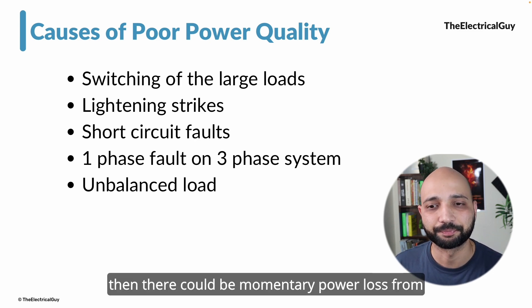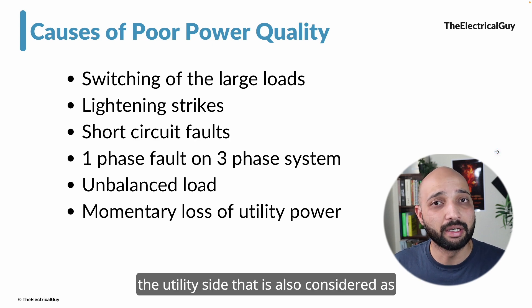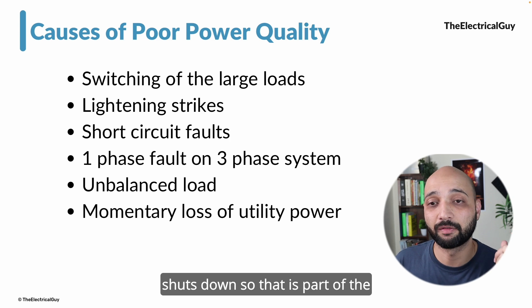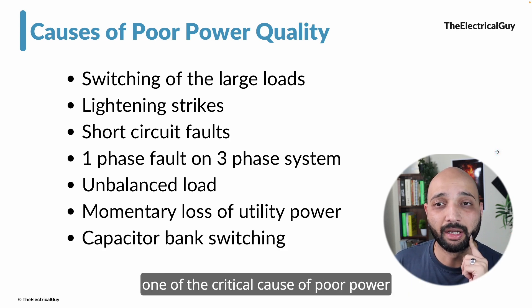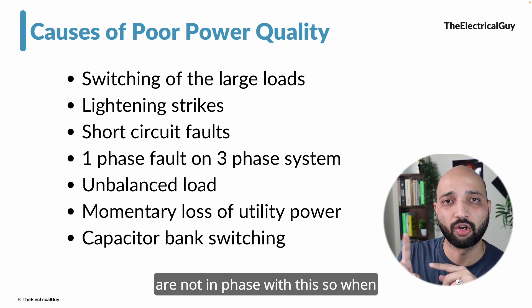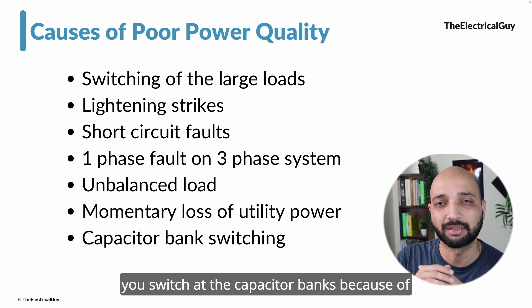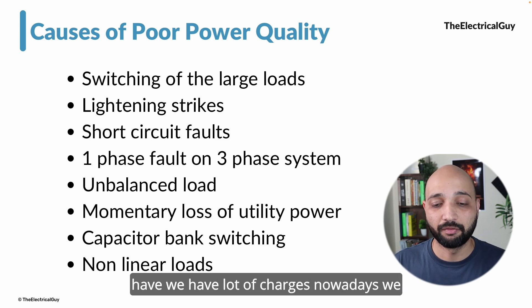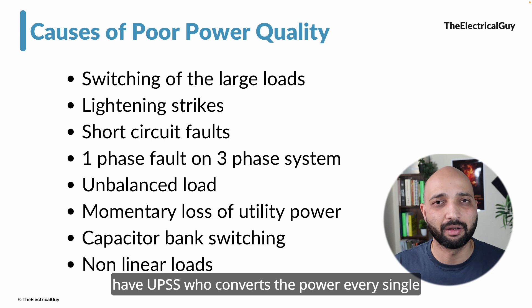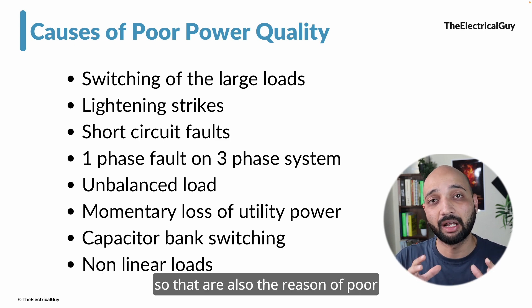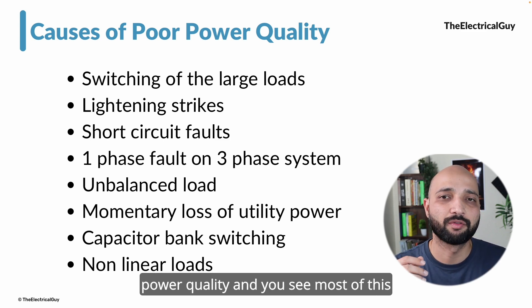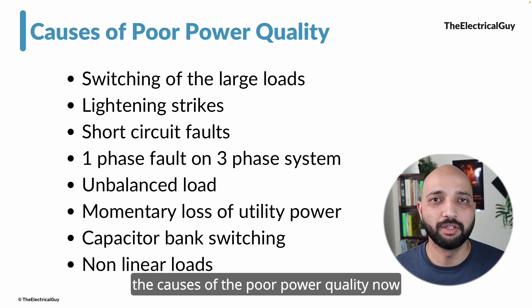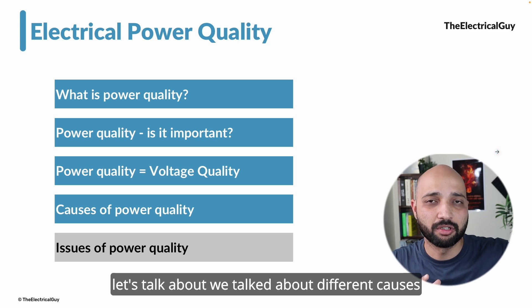Momentary power loss from the utility side is also considered poor power quality, since equipment shuts down when power is lost. Capacitor bank switching is another critical cause — because voltage and current are out of phase, the charging and discharging of capacitor banks causes imbalances. Non-linear loads such as switching devices, chargers, and UPS systems that constantly convert power also cause poor power quality. Notably, most of these causes are not in the utility's control — they must be managed at the customer's end.